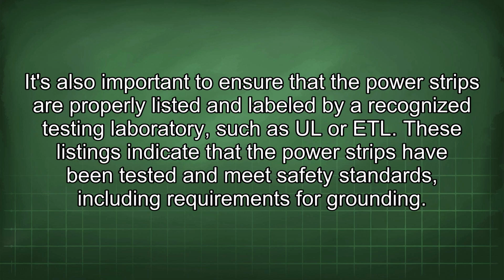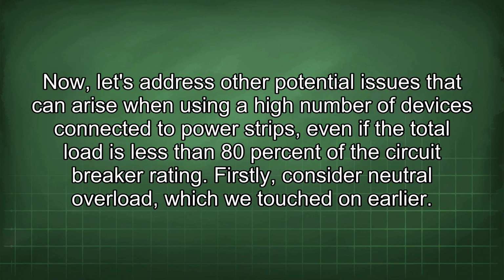It's also important to ensure that the power strips are properly listed and labeled by a recognized testing laboratory such as UL or ETL. These listings indicate that the power strips have been tested and meet safety standards, including requirements for grounding. Now, let's address other potential issues that can arise when using a high number of devices connected to power strips, even if the total load is less than 80% of the circuit breaker rating. Firstly, consider neutral overload, which we touched on earlier.